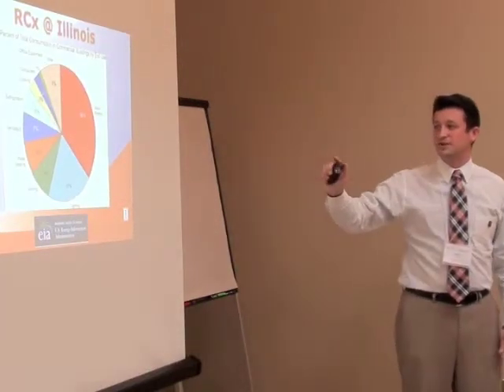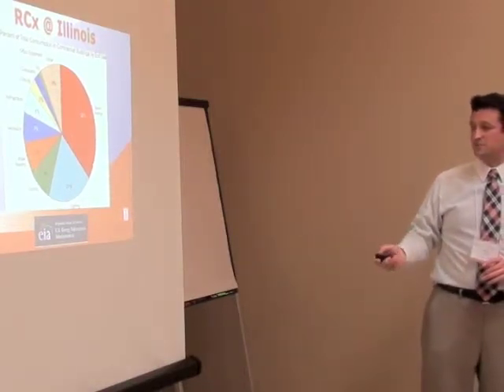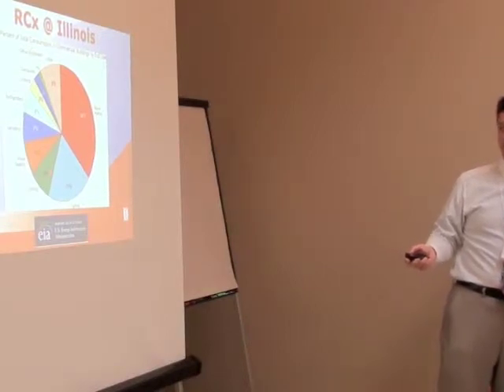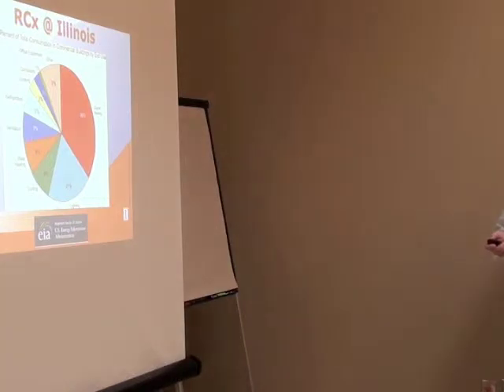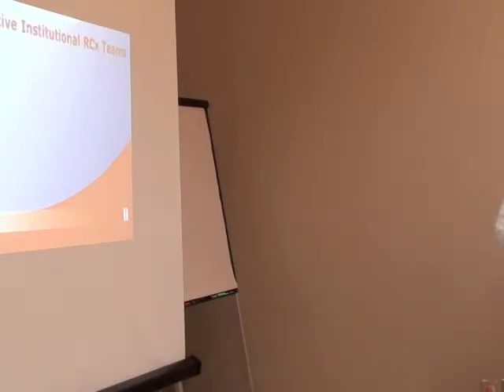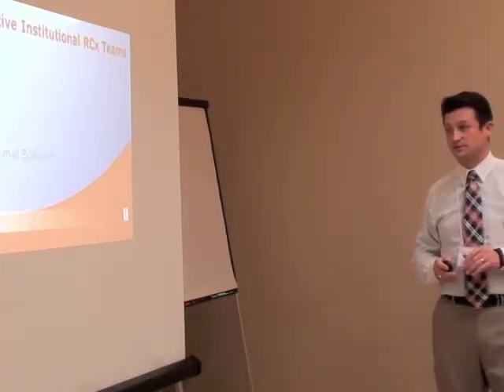So we're going to focus on retrocommissioning. And retrocommissioning in Illinois may be different than retrocommissioning in other parts of the world. When I say that, it's because we have a specified group already taking care of the lighting. So if we add up the other three bigger chunks that we could put together, well, I'm an HVAC engineer, so I look at heating, and then I look at ventilation, and then I look at cooling. If I add those up, I get 51% of the building's energy is going to HVAC, and 21% to lighting. So I'm going to dedicate a team to only review HVAC systems.